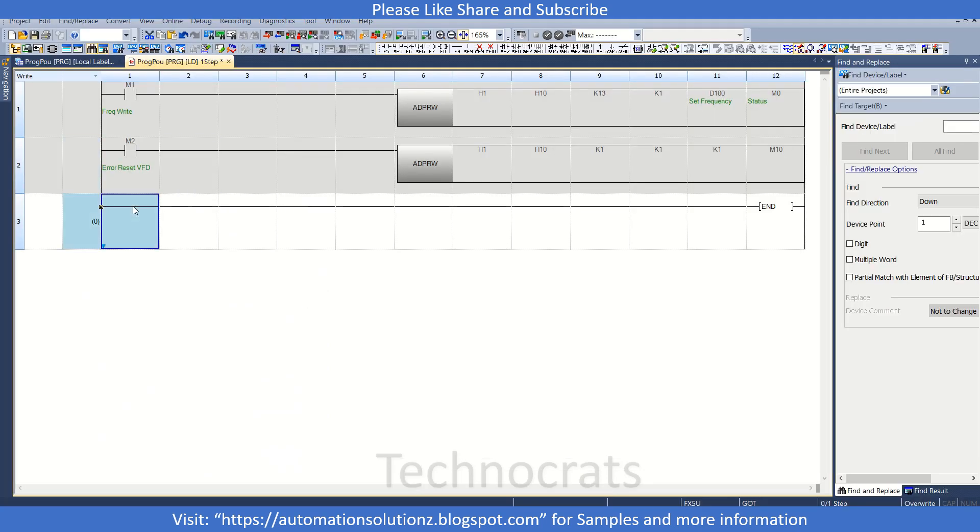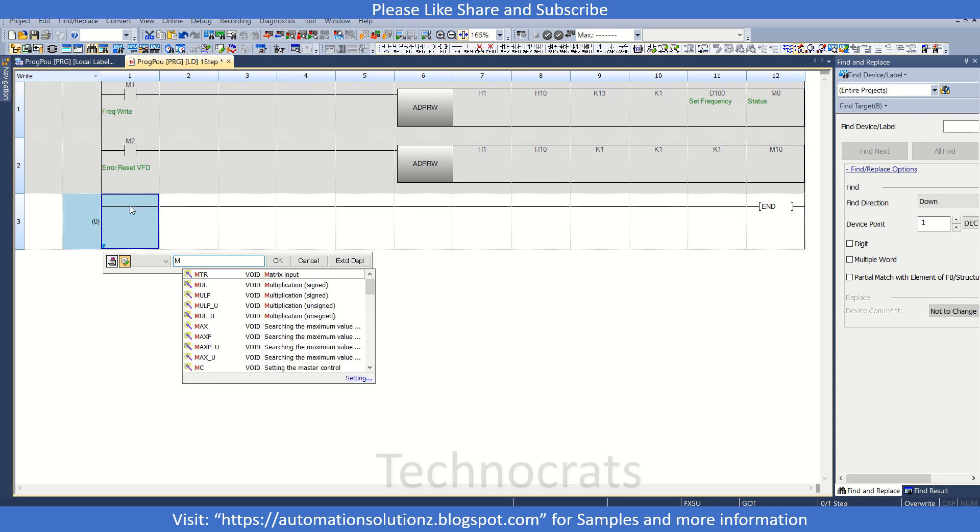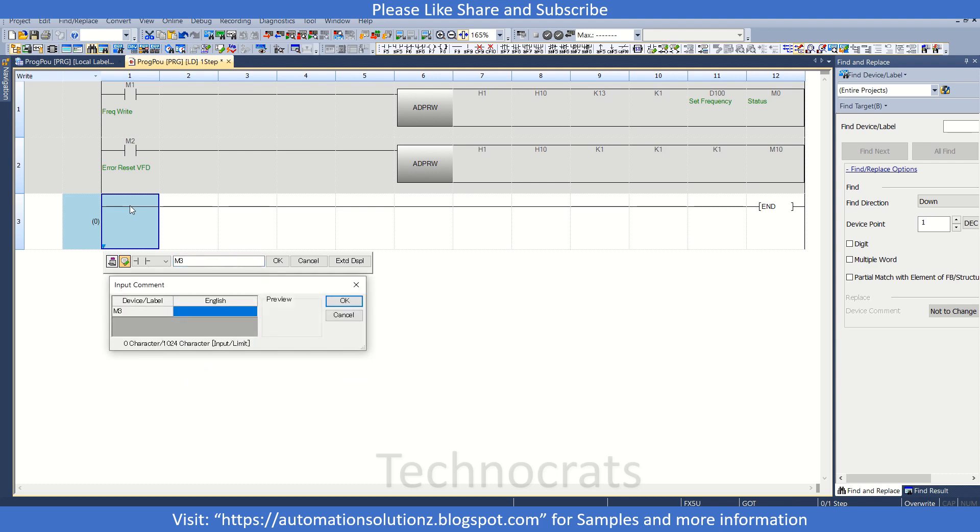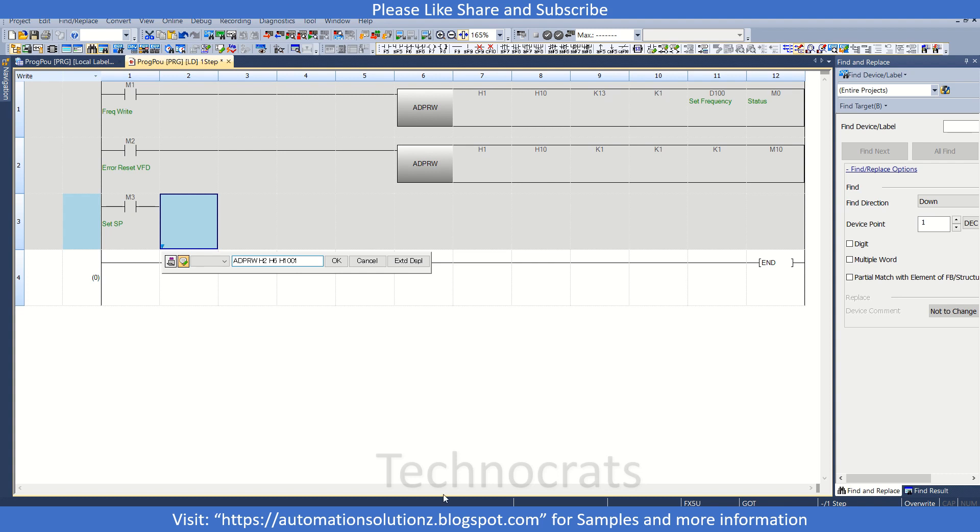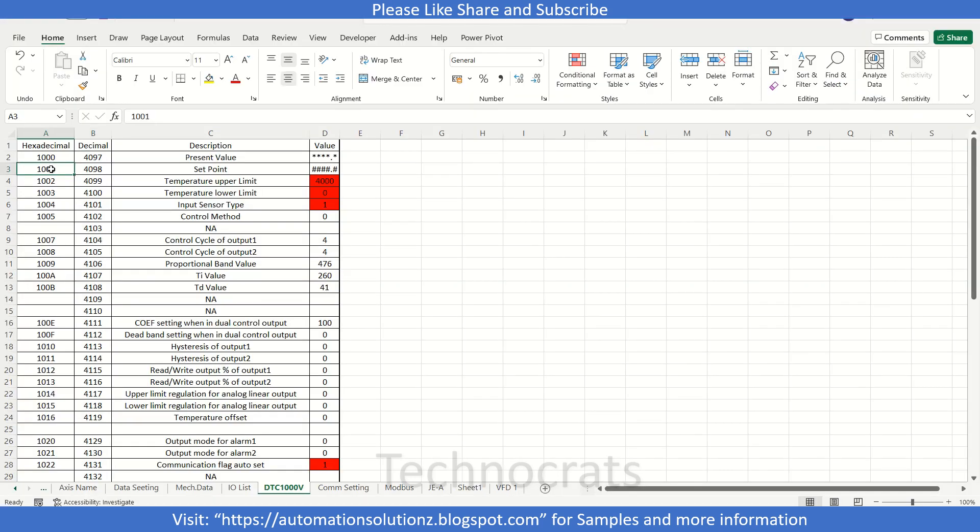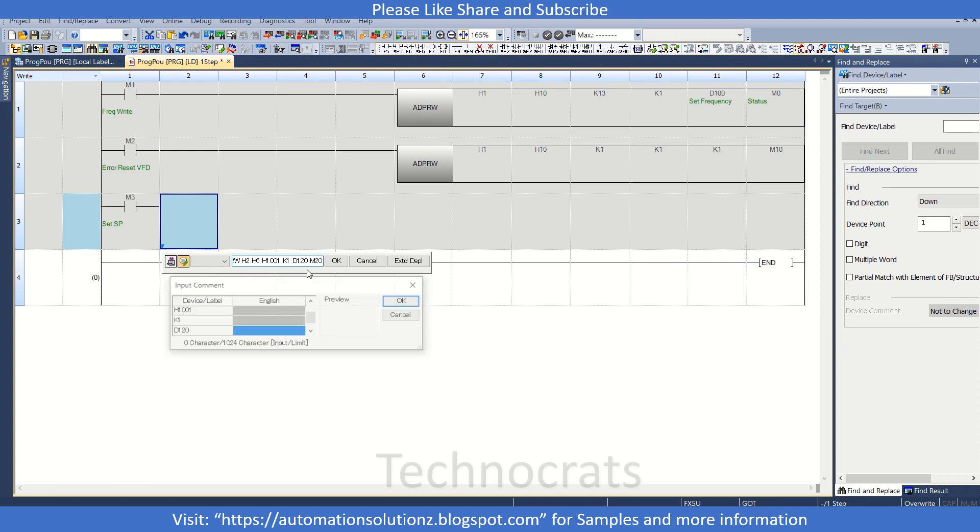Let's see how we can write this. For this I will use ADPRW instruction with my Modbus slave station address, that is H2. Now I have to use the function code, that is H6, and H1001 is your Modbus address. After that I will use K1 and D120, that is your set point value, and then we use M20 as your status code. This is your SV set value.